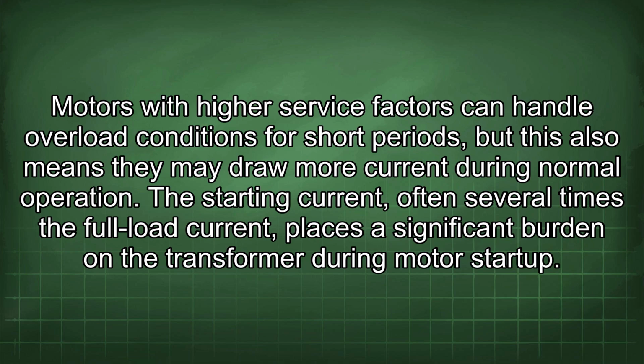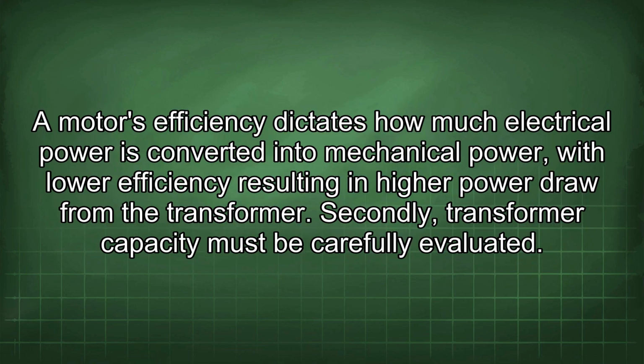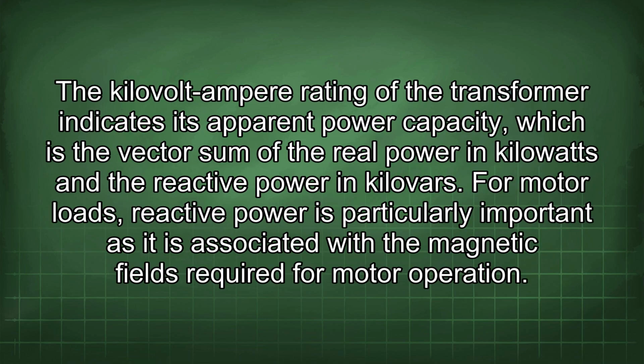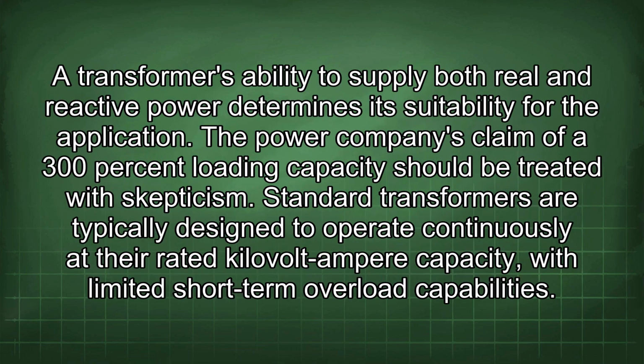The starting current, often several times the full load current, places a significant burden on the transformer during motor startup. A motor's efficiency dictates how much electrical power is converted into mechanical power, with lower efficiency resulting in higher power draw from the transformer. Secondly, transformer capacity must be carefully evaluated. The kilovolt ampere rating of the transformer indicates its apparent power capacity, which is the vector sum of the real power in kilowatts and the reactive power in kilovars. For motor loads, reactive power is particularly important as it is associated with the magnetic fields required for motor operation. A transformer's ability to supply both real and reactive power determines its suitability for the application.